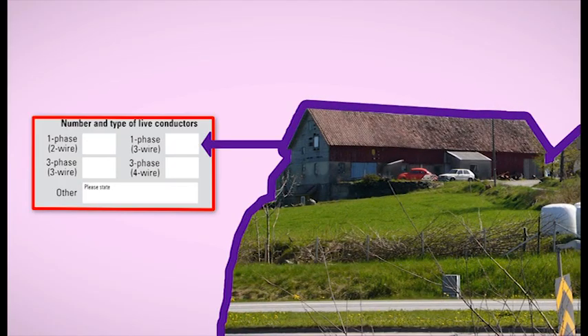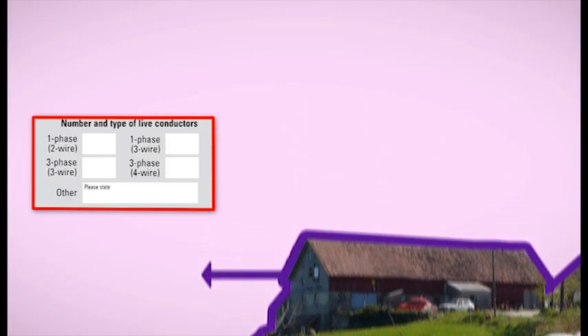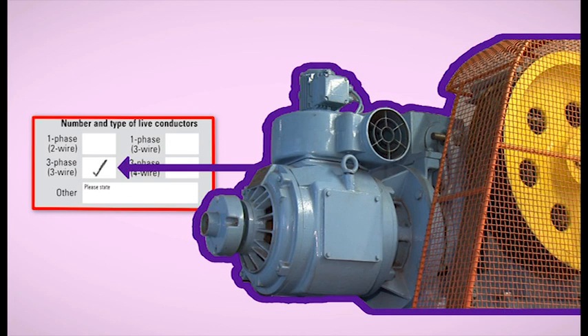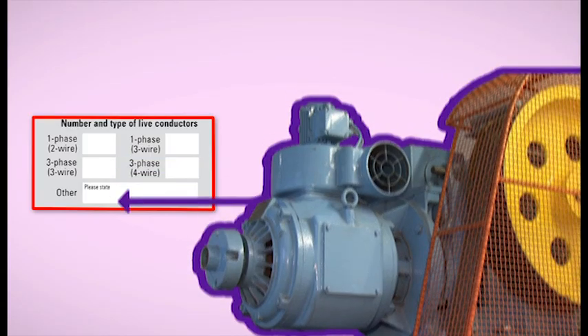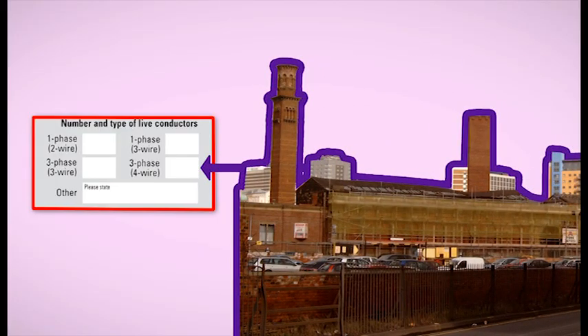One phase 3 wire relates to a single phase split phase supply, 230 to 460 volts. This is not common, but you could encounter it, say on farms, where a higher voltage may be necessary to operate some machinery. Three-phase 3 wire is often used in larger installations to supply motors and has 3 line conductors, one for each phase of the supply. And finally, we have three-phase 4-wire, which has 3 lines and a neutral. This will be for commercial, industrial and the larger domestic installations.